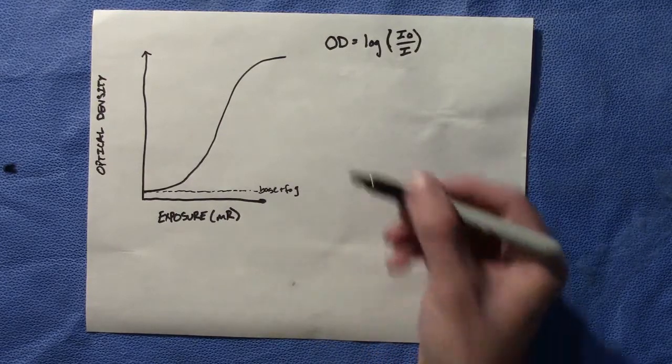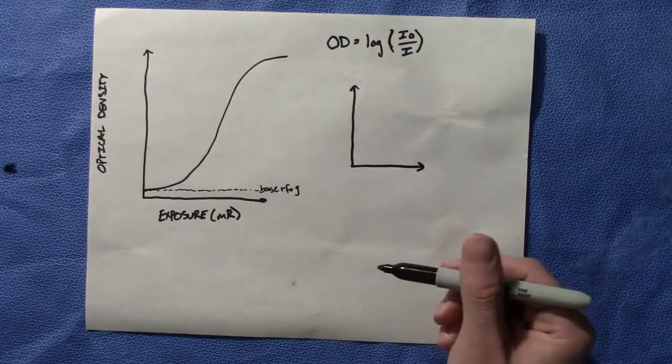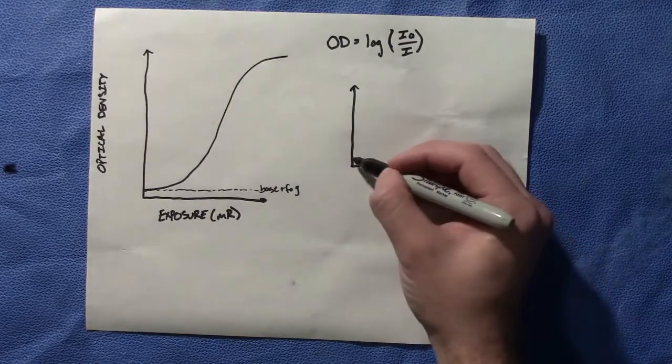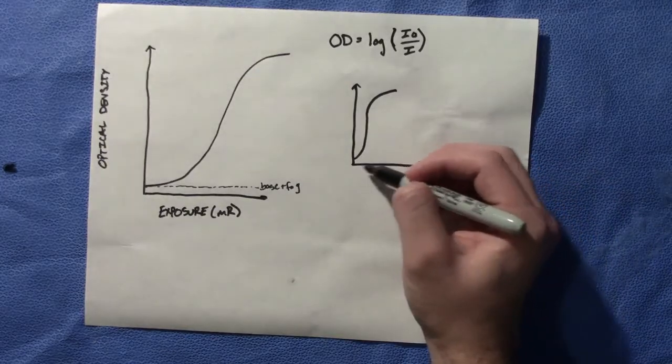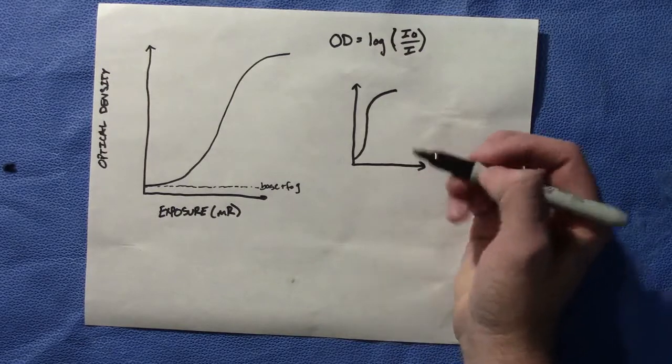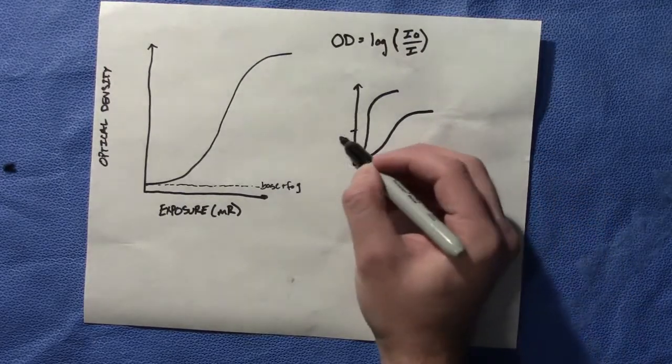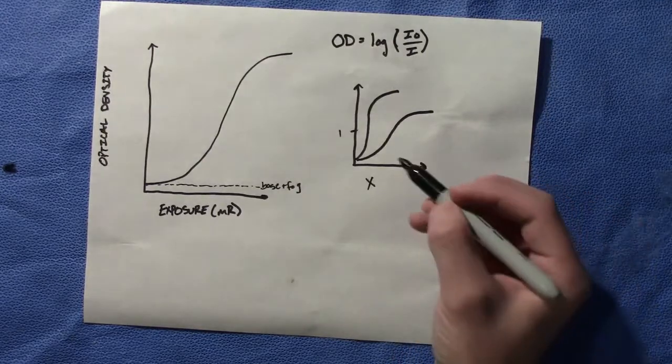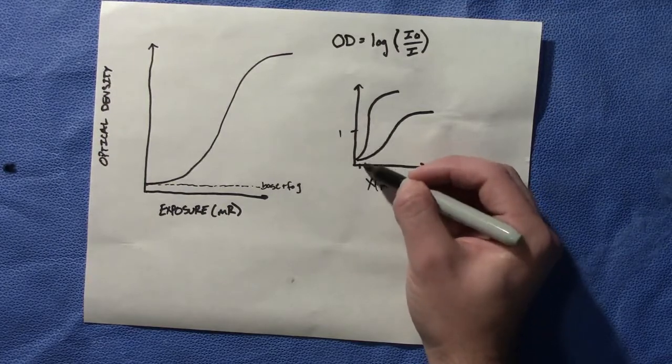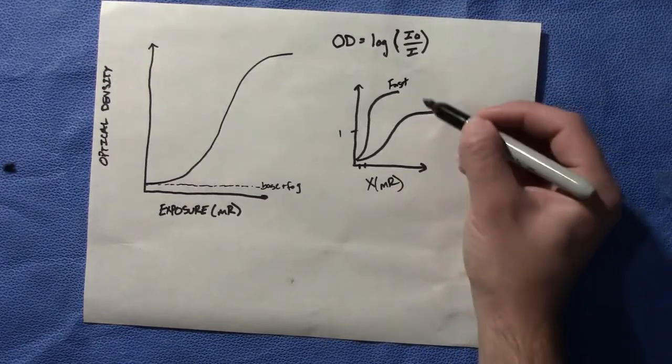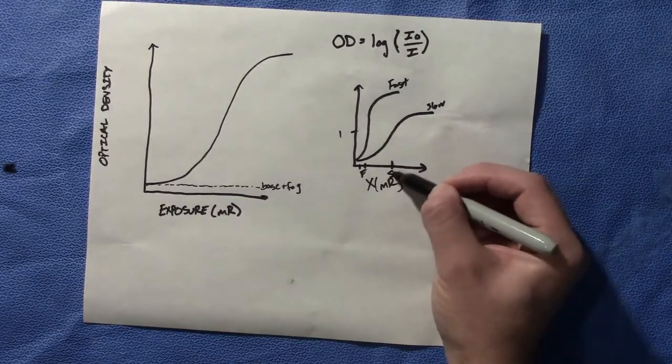A fast film requires little radiation to reach an optical density of one, so it takes very little exposure to hit an optical density of one. A slower film may start with the same base and fog but looks like this. It takes a lot less radiation to hit an optical density of one for our fast film versus our slow film, which requires more exposure for the same optical density.